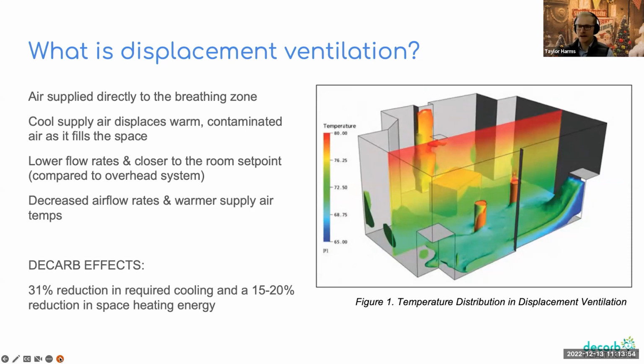Because the air is put into the room much closer to the breathing zone, the ventilation effectiveness is much more effective, which allows you to use lower airflow rates. That combined with the warmer supply temperatures leads to much lower reheat and cooling energy needed to condition the space. And this can result in a 31% reduction in cooling and 15 to 20% in space heating energy savings.